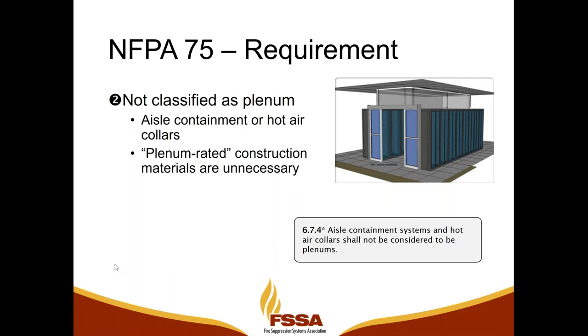Speaking of plenums, point number two in NFPA 75 is that aisle containment systems are not classified as plenums. The volumes in the room as we break them down shouldn't be considered by a fire marshal or other authority having jurisdiction as a plenum space. And the code reads 6.7.4, aisle containment systems and hot air collars shall not be considered to be plenums. So that's one of those call off the dogs sections, where we are telling AHJs that this is not a plenum. So not all materials in here need to be plenum rated.